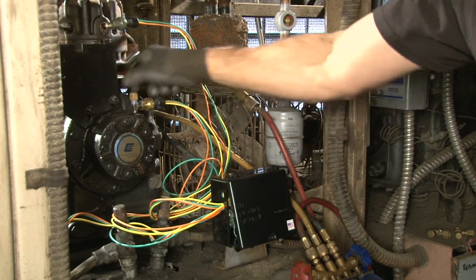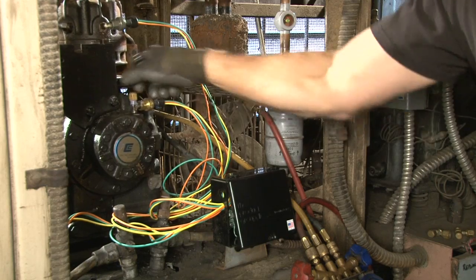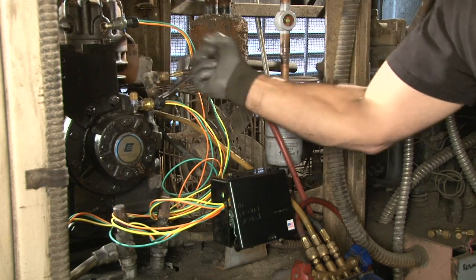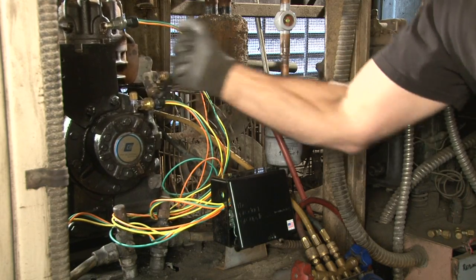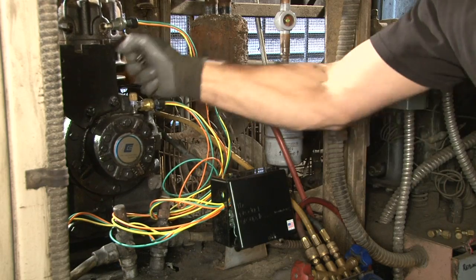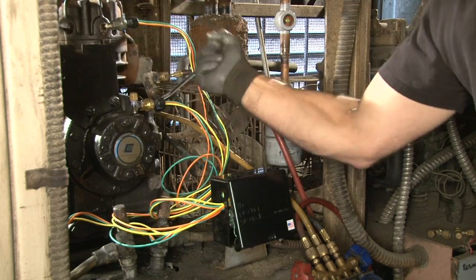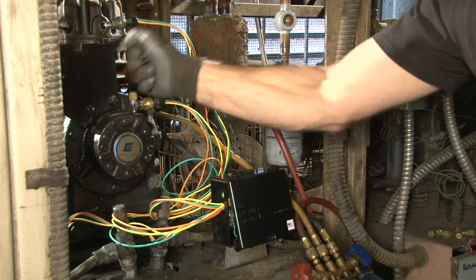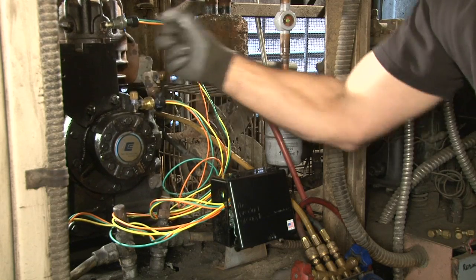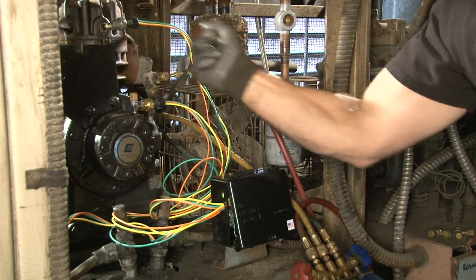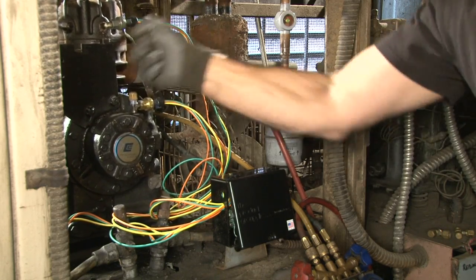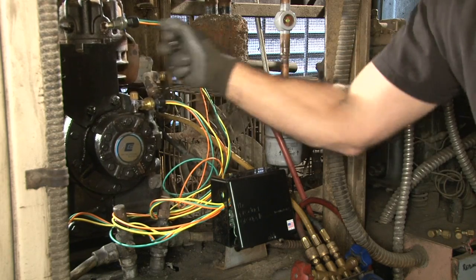Now the technician is opening the discharge access valve stem, allowing the refrigerant to pass into the compressor body, having previously evacuated the air from the compressor body itself. This is in preparation to start the compressor system.